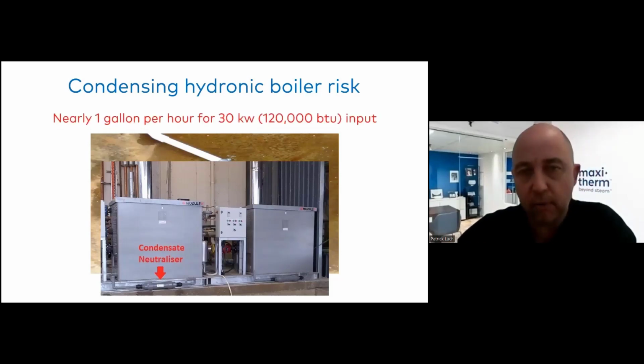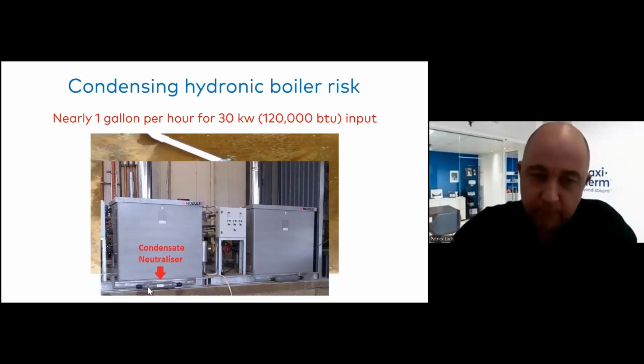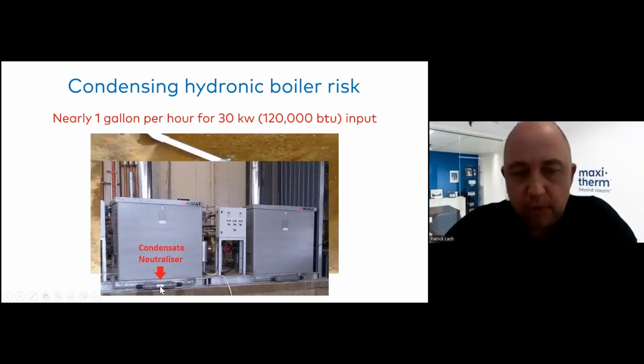So did you know that number? Nearly 1 gallon per hour for 120,000 BTU input. You will dump a gallon per hour. So if it's a 5 million BTU unit, it's a lot of gallons per hour. Right? How many of those units are there downtown in your city? Dumping acid to drain, because don't get me wrong, the first year, everybody remembers what it is. In 5 years, nobody remembers what it is. That little feature here.